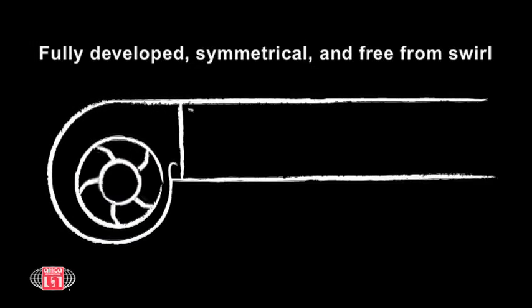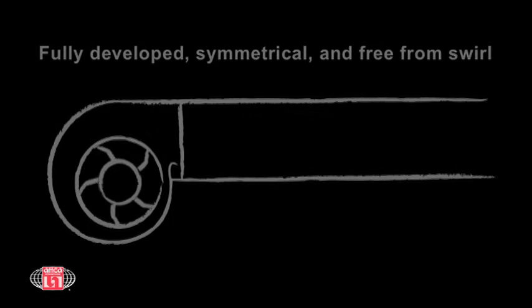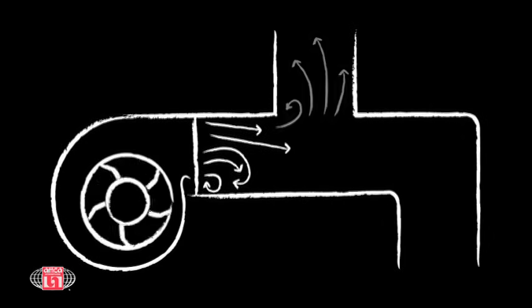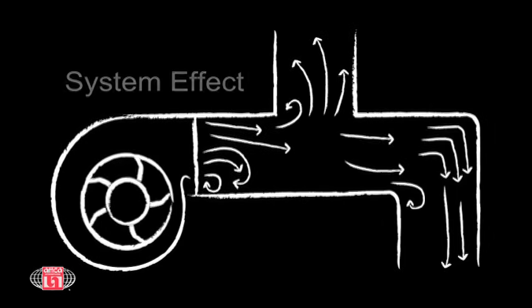For optimum system performance, the air flow at the inlet must be fully developed, symmetrical, and free from swirl. Ducting on the outlet needs to be designed so that the asymmetrical flow profile from the fan is allowed to diffuse and approach fully developed flow. The effect on fan performance when these conditions are not met is called system effect.